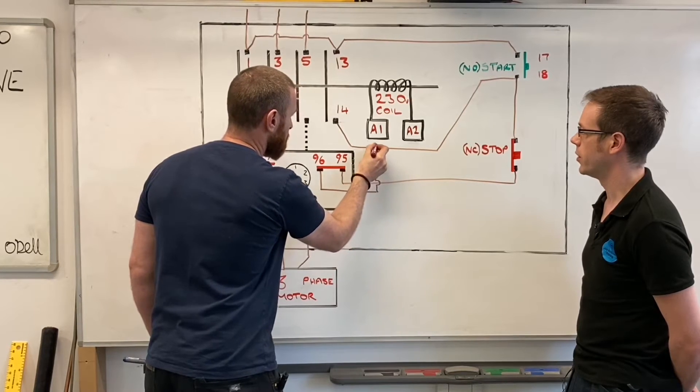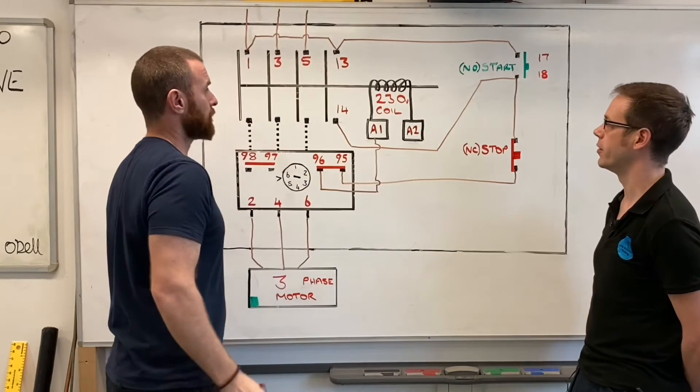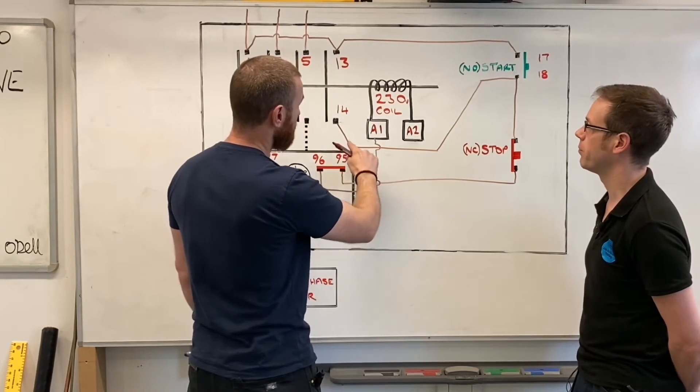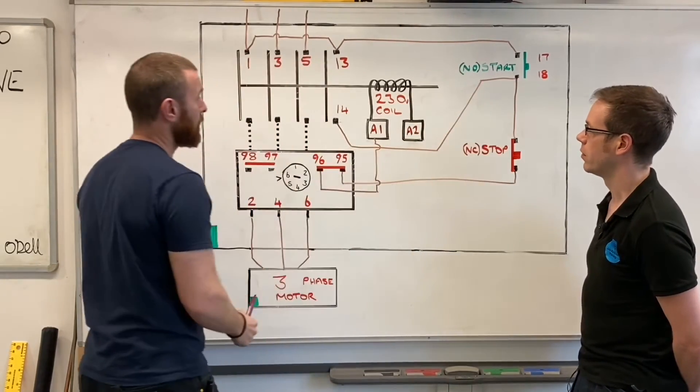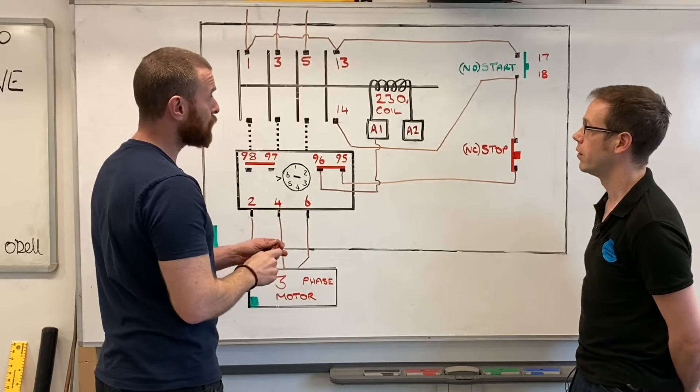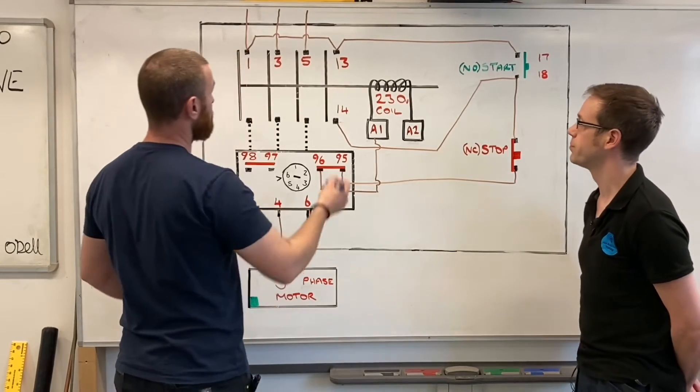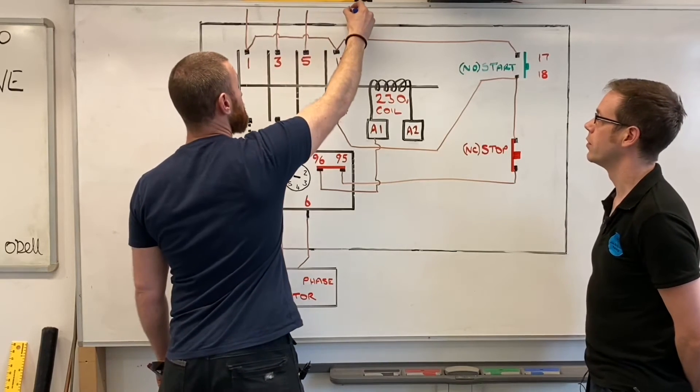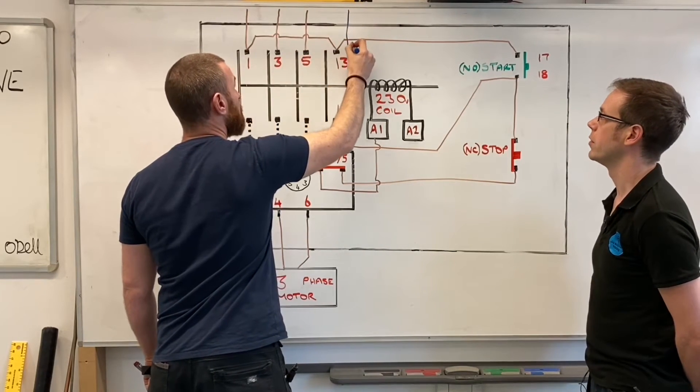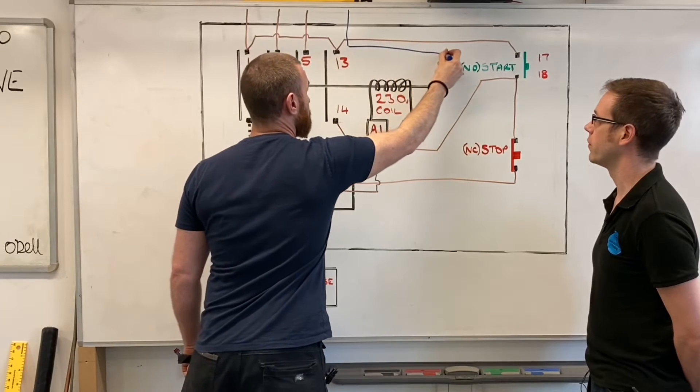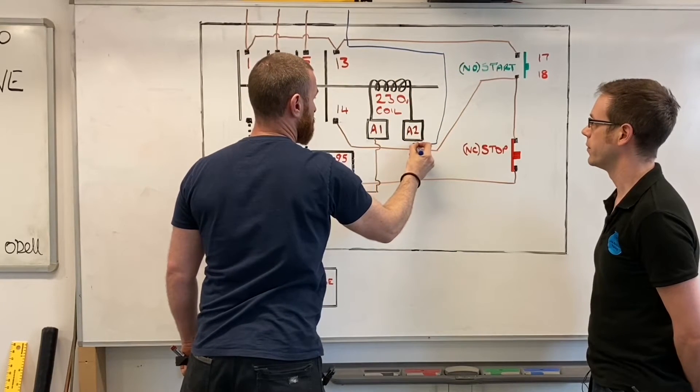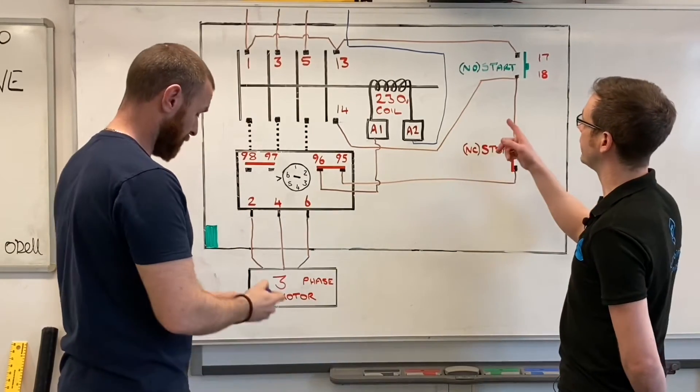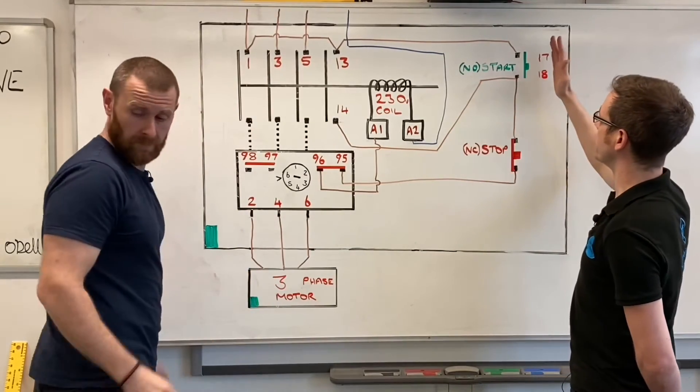We're going from 96 back, and then we're going to go to A1 there. That's where we've got before, that's exactly the same. We've got our circuit going through there. The only thing that's missing is our neutral conductor. This time the neutral's got nothing to do with any of the terminations. The neutral just simply comes in as a separate conductor there, and then into terminal A2.